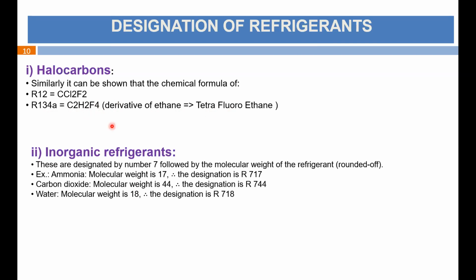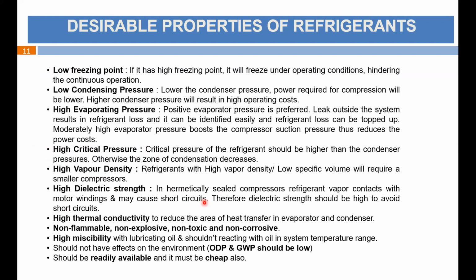So it is tetrafluoroethane. Similarly, inorganic refrigerants are designated by 7 followed by the molecular weight of the refrigerant. Like ammonia, an inorganic refrigerant. Its molecular weight is 17, so it is designated by 717. Similarly, carbon dioxide, molecular weight 44, is designated by 744. Water, similarly, is 718. So very basic, but just to refresh your knowledge, I added this slide.